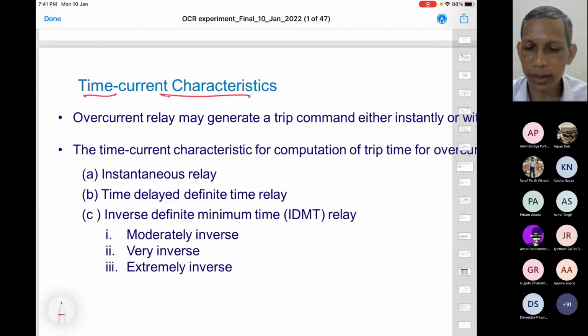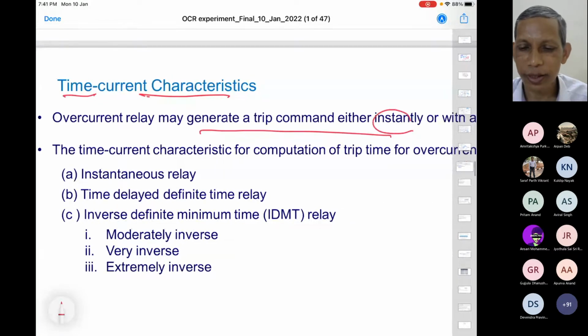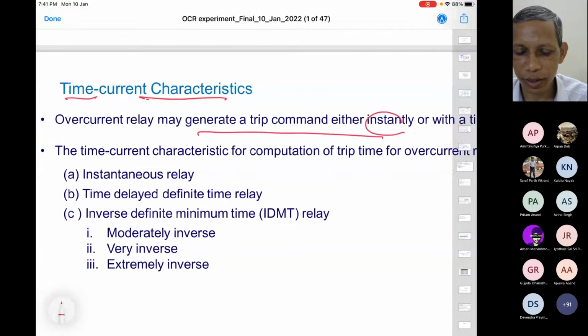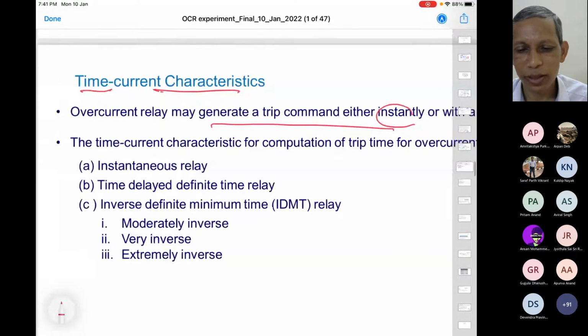Agree? Overcurrent characteristic. Now you see here, overcurrent may generate a trip command either instantly or with a delay. We reason out what the reason for delay is also. If the fault is not permanent, why not wait and watch for some time.